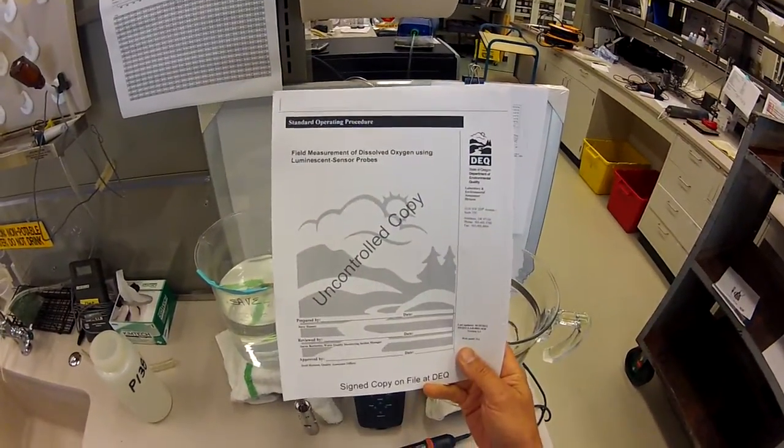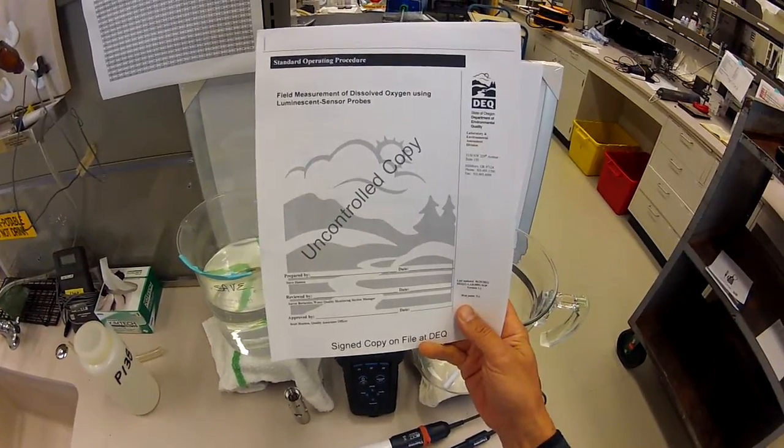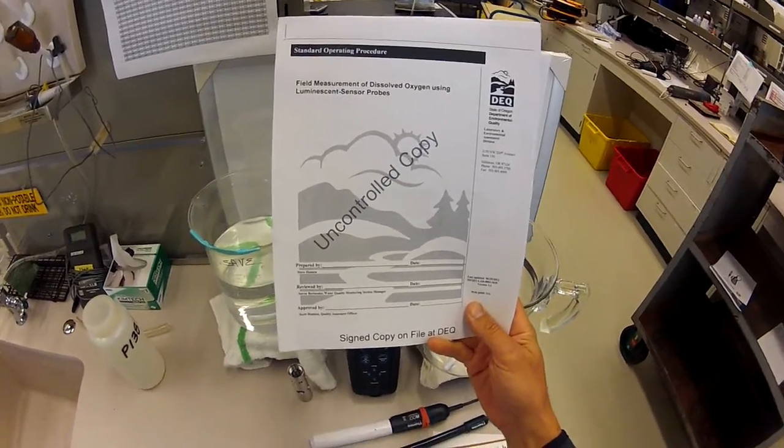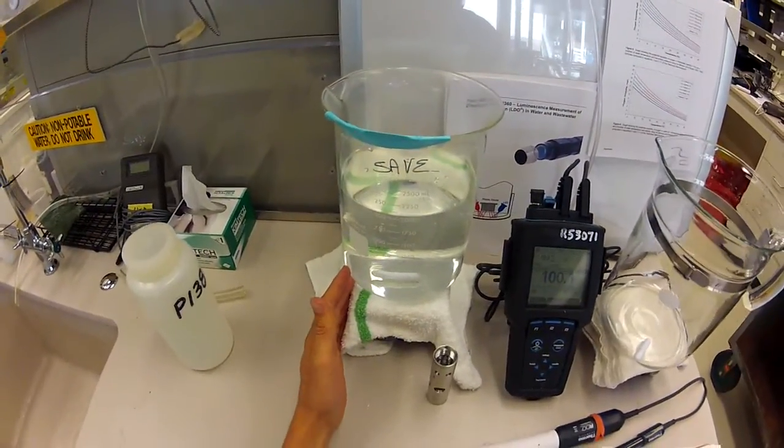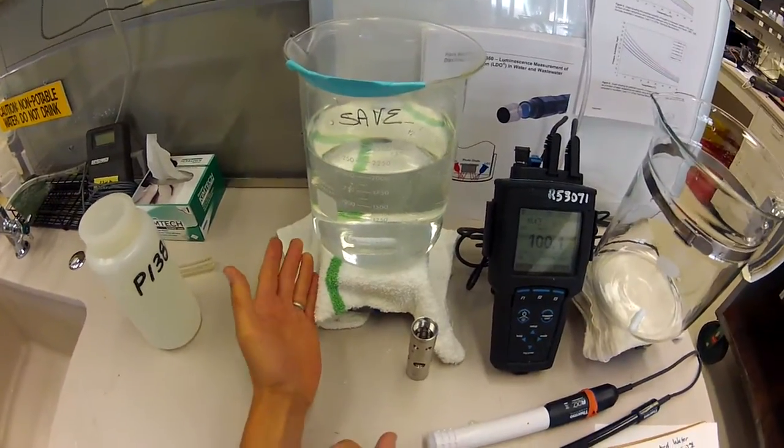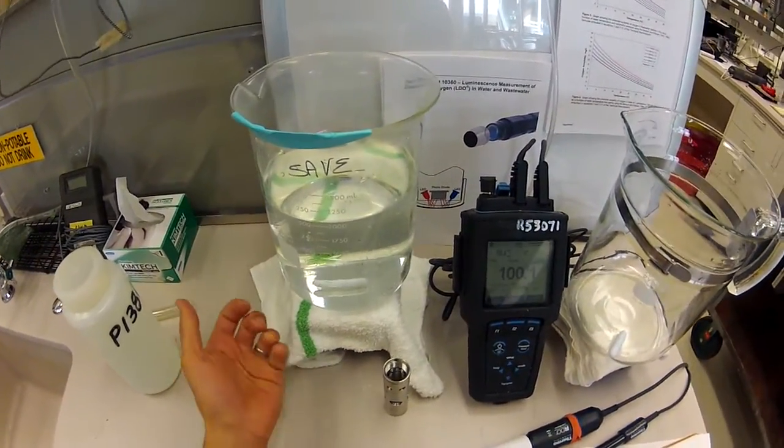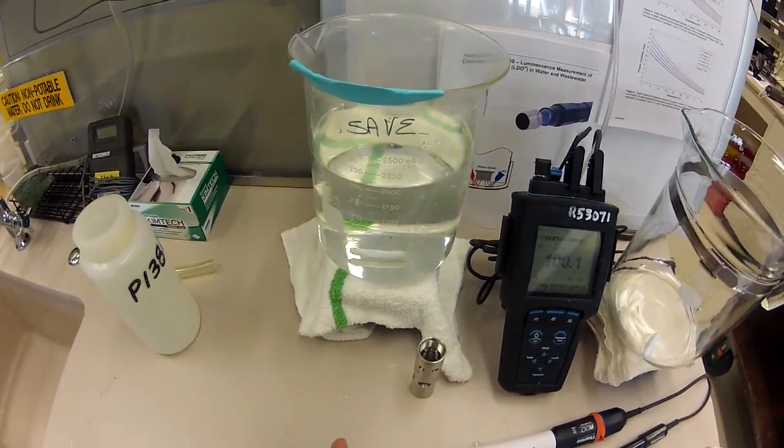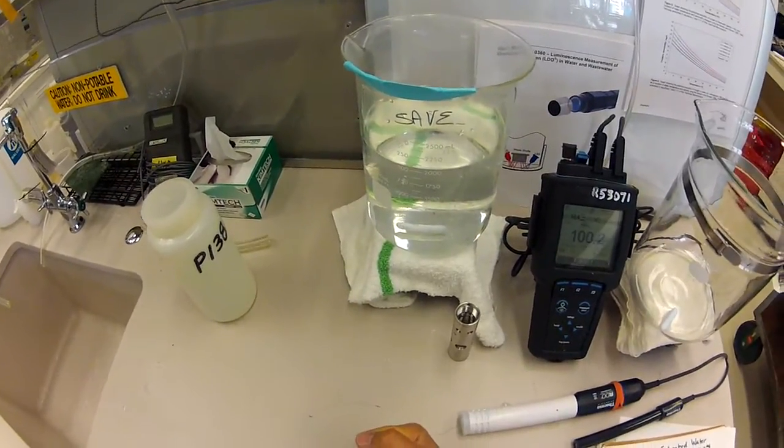I'm going to be following the standard operating procedures from the Oregon Department of Environmental Quality Labs for these types of probes. We're going to use this standard to verify calibration. It's essentially an accuracy check that you want to do before and after doing field measurements to document that calibration has stayed true over the course of a sampling period.